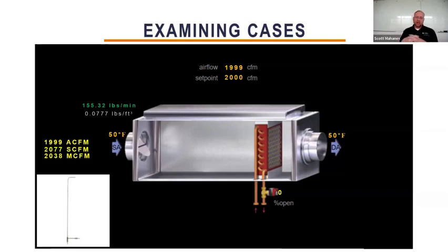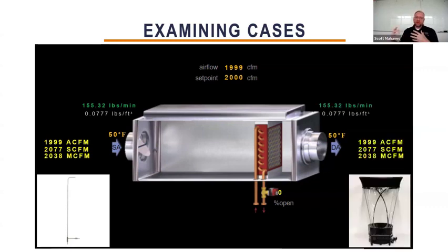Now, I don't want to complicate things, but what I'm trying to show is there are three distinct different values of airflow in this example. There's the measured flow rate, which is partially compensated and not fully correct. There's the fully corrected compensated airflow reading of 1999. And yet there's also an airflow rate of 2077. It gets confusing, but that's what really exists at all times. We just didn't realize the SCFM value was there. What's also interesting about this example is I could use a different method of measurement, and I could use a flow hood on the discharge side, assuming it has no leakage. And I should come up with the same values, right? I should measure 2038 on the meter with no temperature probe compensation. If I compensate it, I get 1999. And then if I go to a mass flow conversion, it's 2077.